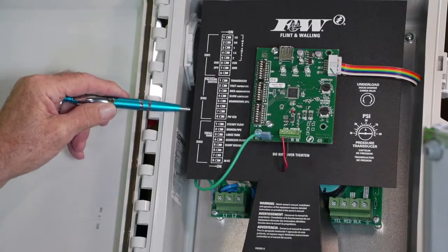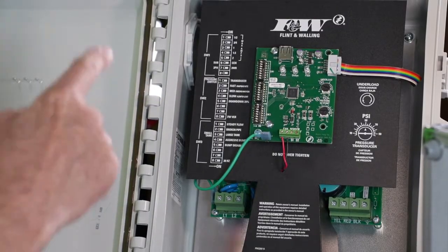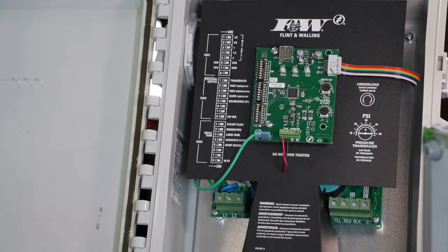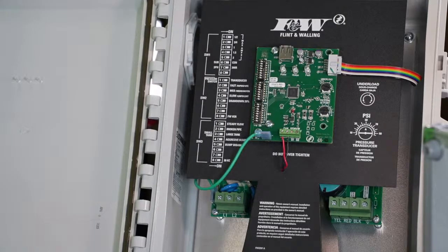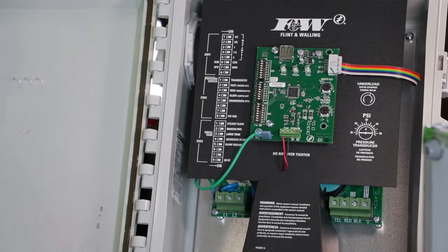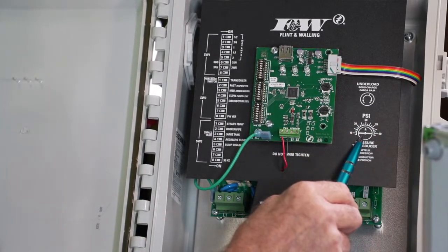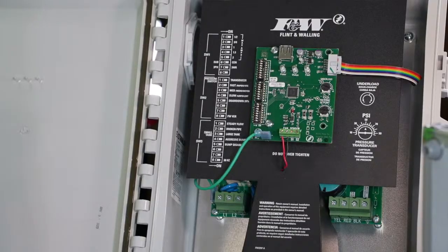That second bank, SW2, that's got to do with what are we going to use to turn that pump motor on. We talked about that briefly a second or 2 ago, whether it's going to be a switch or a transducer. And then that bank 3 down there, that's your catch-all, that's kind of your fine-tuning. Again, we'll cover some of that as we get there. And then over on the right-hand side of the drive is the underload dial, and then the pressure dials there. Okay, I'll circle back on both of those. So underload up here at the top, and here's where we're going to set the pressure down here at the bottom. All right. So again, that's pretty much the basic inside of this drive.